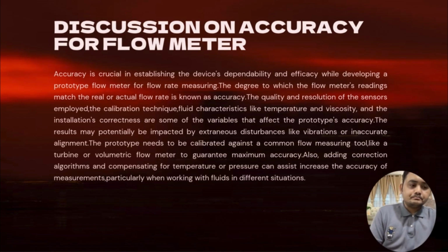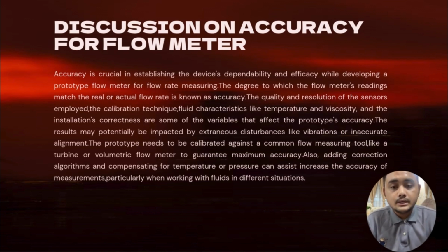So next in the discussion for the flow meter, we have factors affecting the accuracy of a flow meter. Several factors can influence a flow meter's accuracy. First is installation, like poor alignment, vibration or insufficient straight pipe runs, which can cause measurement errors. Second is fluid characteristics, changing temperature, pressure or viscosity can affect accuracy, especially for mechanical meters. Last but not least, calibration: without regular calibration, even a highly accurate meter can drift and give incorrect readings.